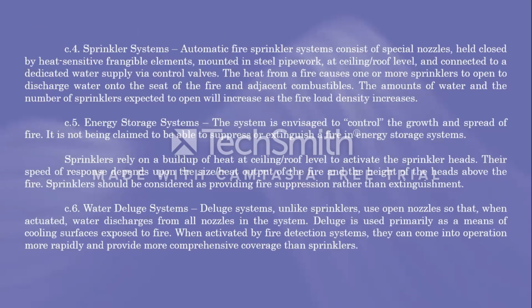Other than that, there are also sprinkler systems. Automatic fire sprinkler systems consist of special nozzles held closed by heat-sensitive frangible elements mounted in steel pipework at ceiling or roof level and connected to a dedicated water supply via control valves. The heat from a fire causes one or more sprinklers to open to discharge water onto the seat of the fire and adjacent combustibles. The amount of water and the number of sprinklers expected to open will increase as the fire load density increases.